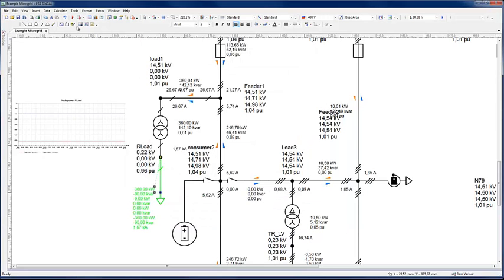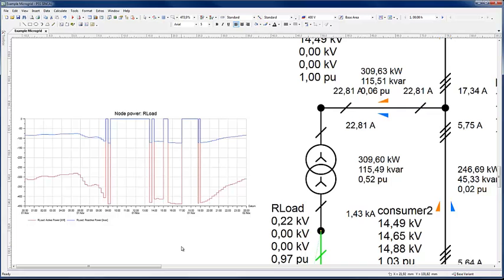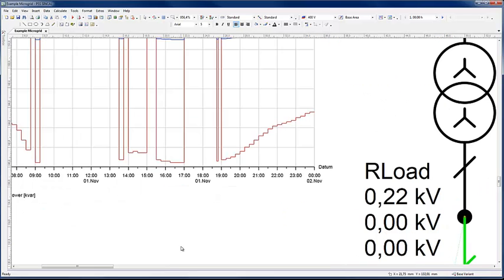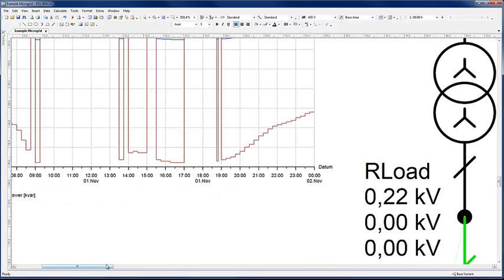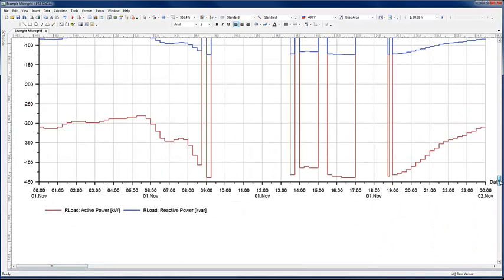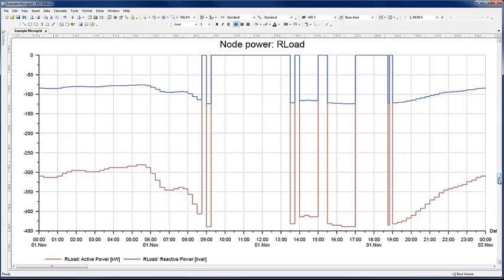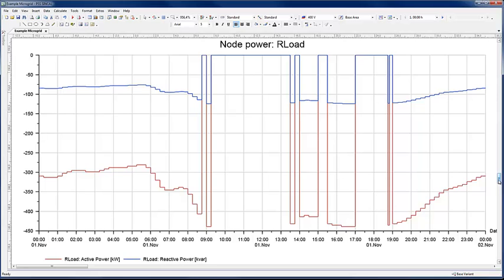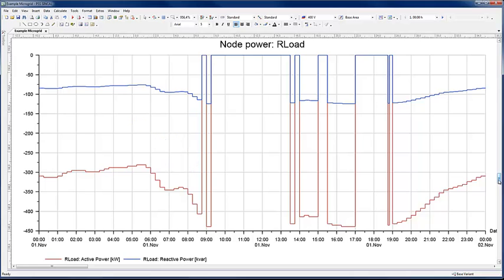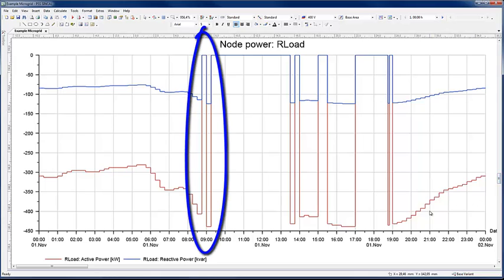Now run the load profile simulation. The resulting load on the node R load now varies according to the profile, increasing gradually at the start. At around 9, the load increase has led to a voltage drop outside the permissible range.